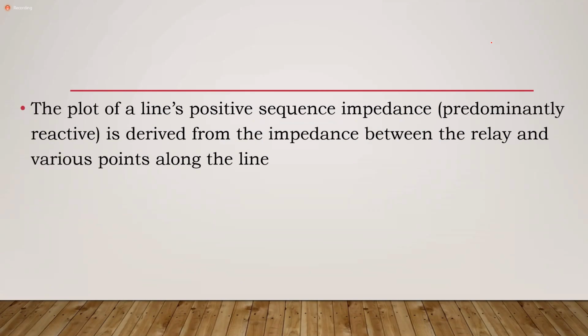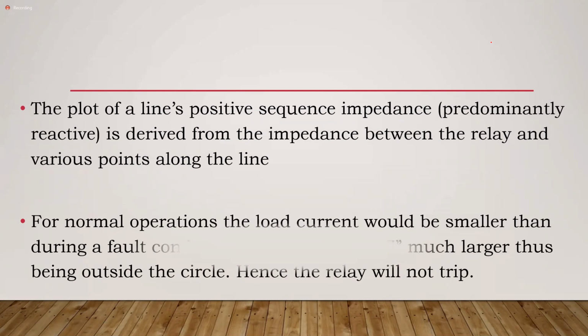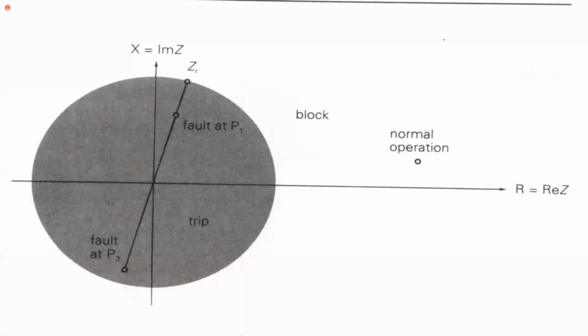The relay would therefore operate. You don't have to worry too much about this, but the characteristic is what I would have given you in the final figure, which is shown. All right. So ZR would be a setting impedance. And anywhere in this region, if you measure an impedance in this region, it will trip. So if the impedance is less than that ZR that you have set, your relay trips.